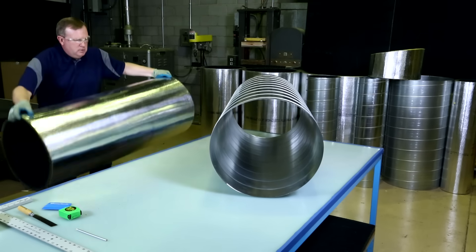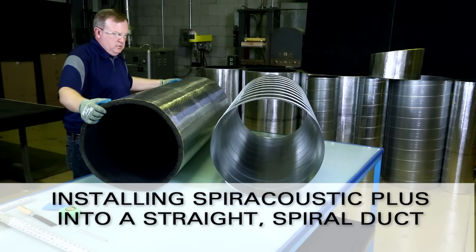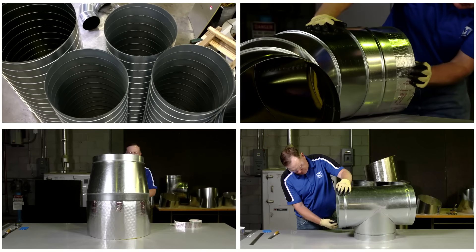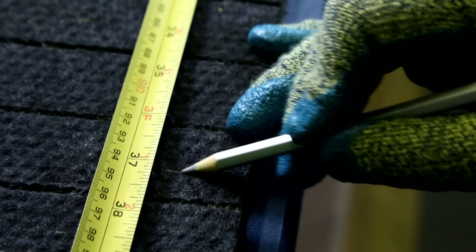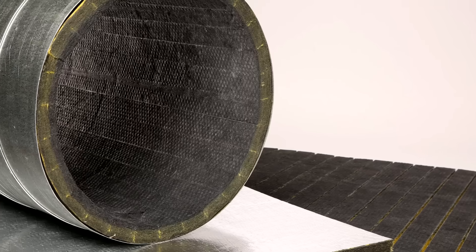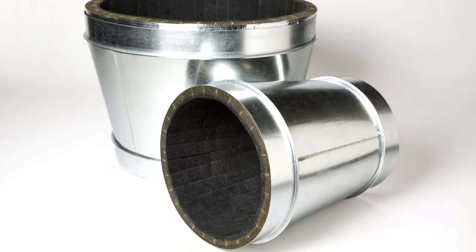The first installation technique we will discuss is how to install Spiracoustic Plus in a straight spiral duct. First, ensure that you have a clean and dry work surface. Also note that for each Spiracoustic Plus fitting, you will want to reduce the circumferential measurement of the duct by approximately 3/4 of an inch when you measure and cut the insulation. This will ensure that the Spiracoustic Plus fits snugly inside the duct or fitting.